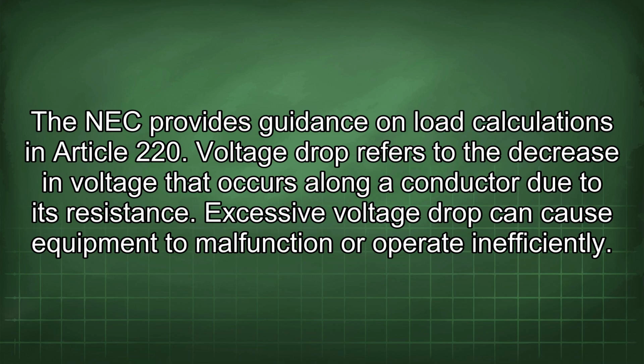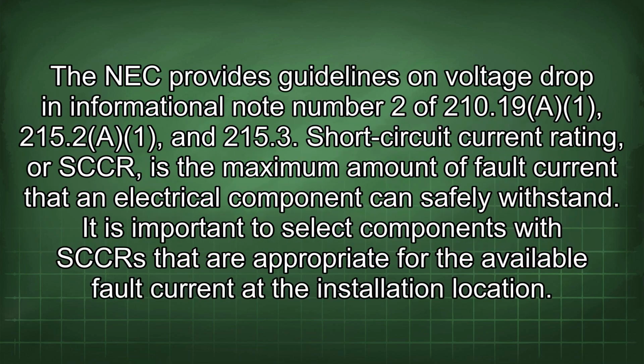Voltage drop refers to the decrease in voltage that occurs along a conductor due to its resistance. Excessive voltage drop can cause equipment to malfunction or operate inefficiently. The NEC provides guidelines on voltage drop in Informational Note Number 2 of 210.19(A), 215.2(A), and 215.3.